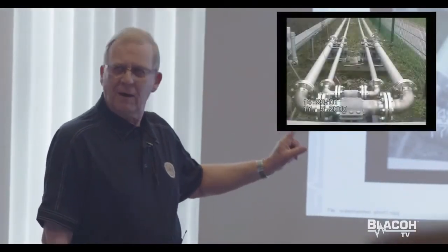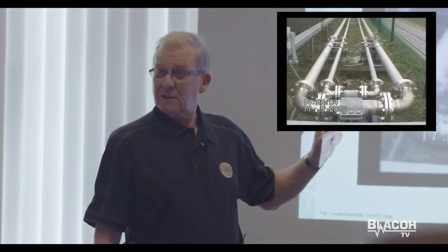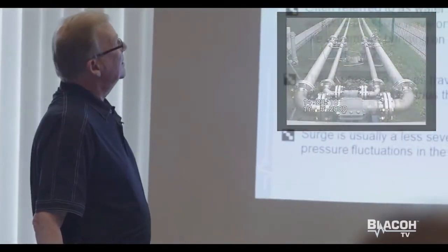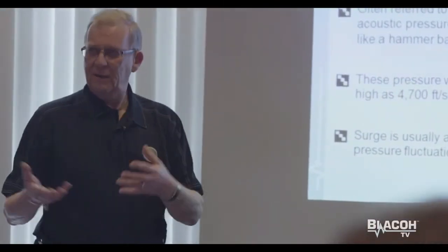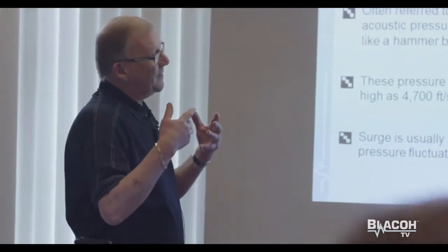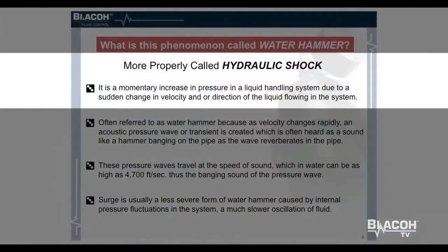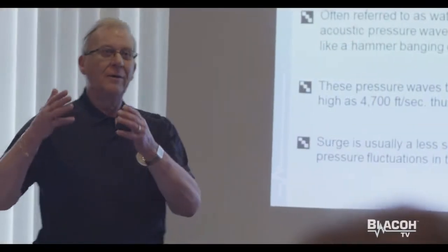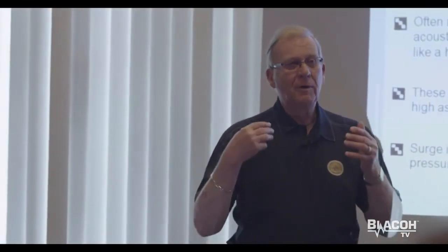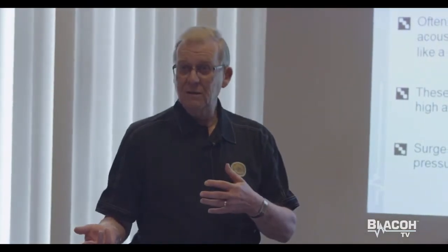Now pay attention to this because two things are going on. Hydraulic vibration and acoustics. So what is this phenomenon? It's hydraulic shock. It's a momentary increase in pressure in a liquid system due to the sudden change in velocity of a fluid. That's the key point. It's not necessarily stopping the fluid, but a rapid change in velocity.